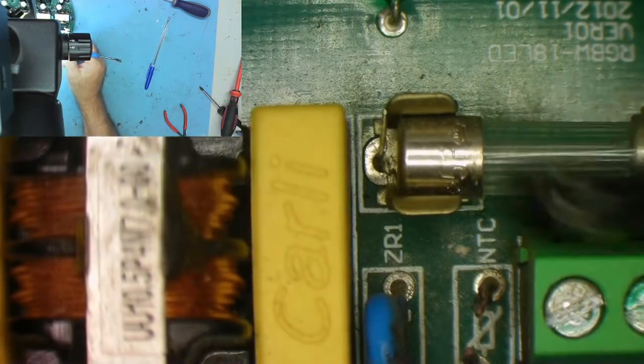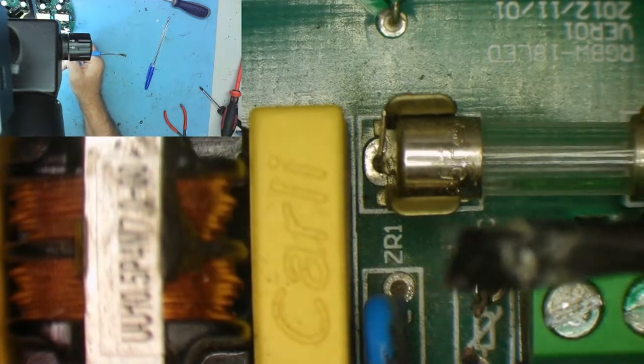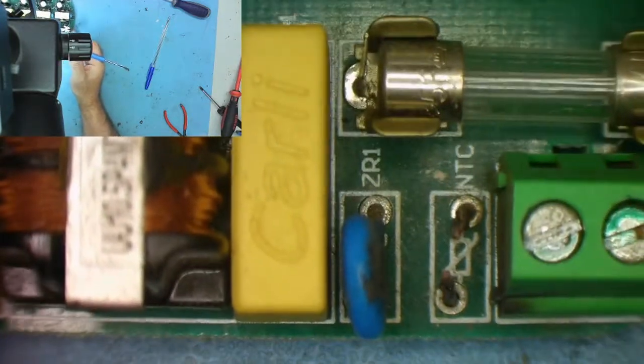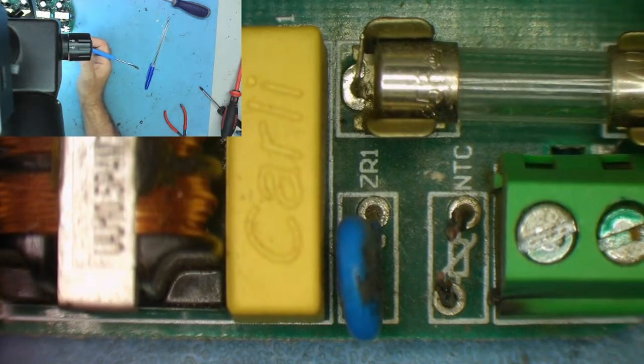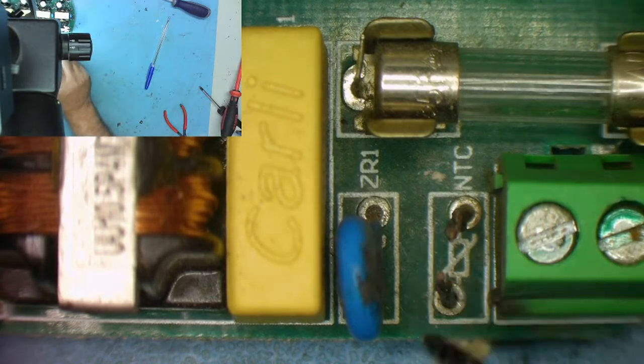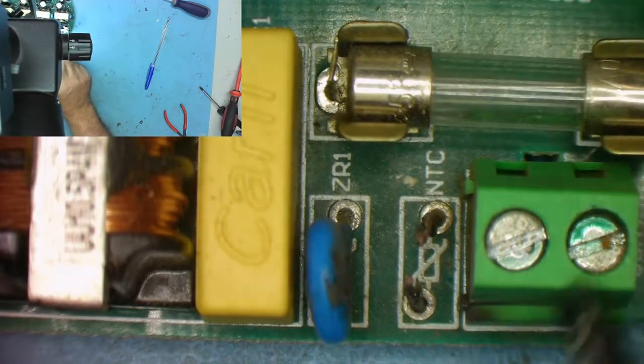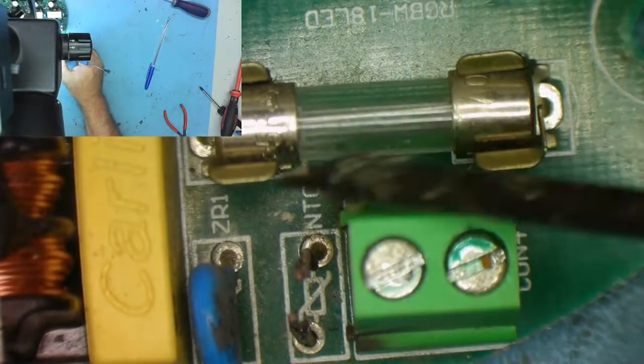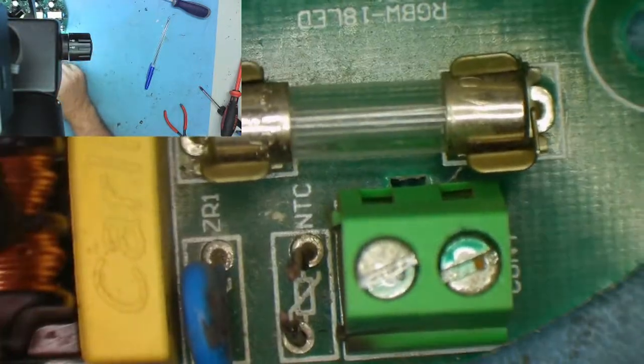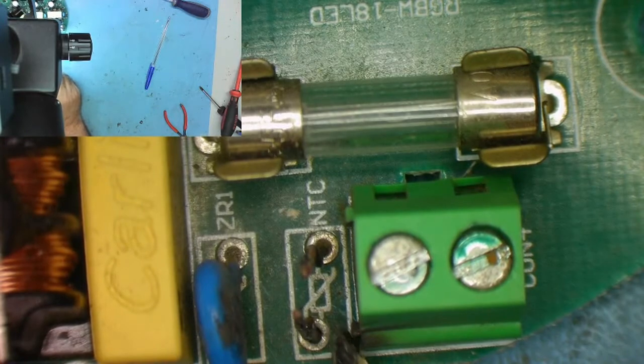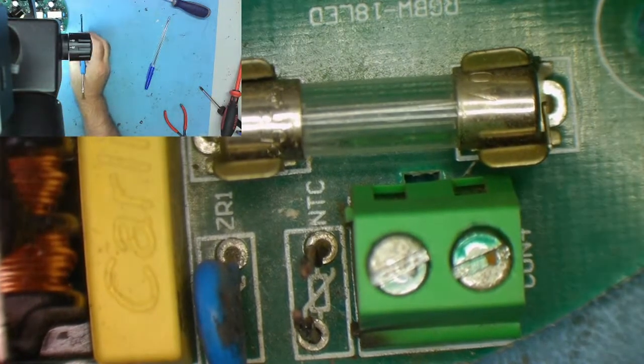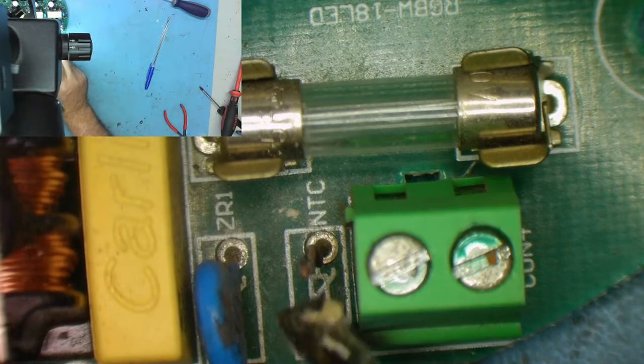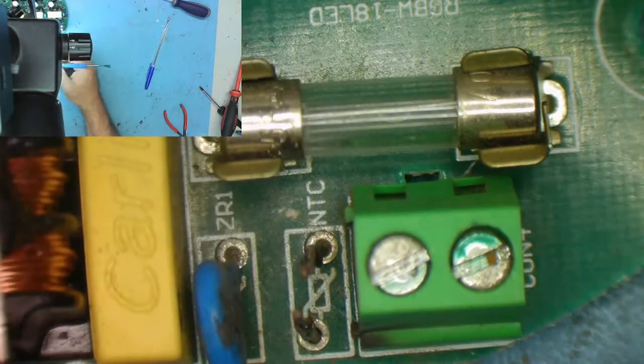But anyway, the fuse is designed so it can withstand this inrush of current. It only lasts less than a second or so. This starts off at a relatively high value, and it limits the amount of current that comes into the capacitor. That's why the fuse doesn't blow. It doesn't blow on the inrush because this limits the inrush. If this wasn't there, the fuse would probably blow. So this starts off at a high value and power sort of trickles into it.